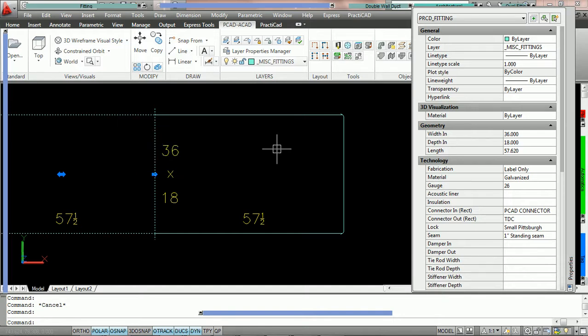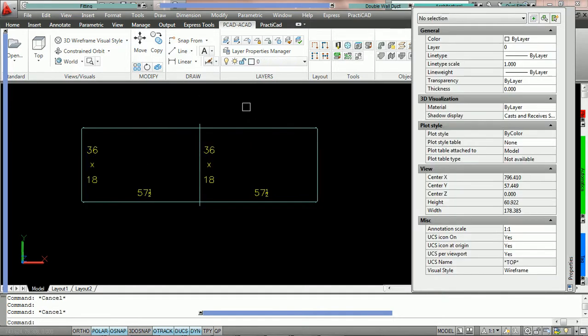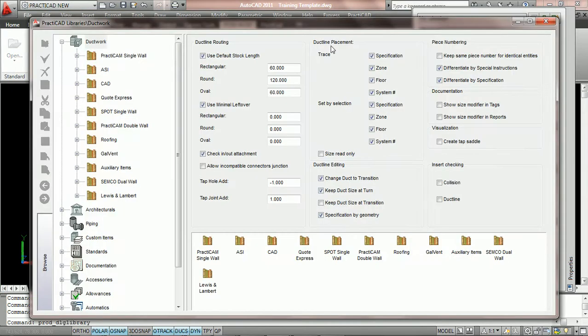Now, one thing to keep in mind is that the entire mechanism we just showed you will only work in this manner if in your ductwork options you have the Allow Incompatible Connectors option unchecked. And we have separate tutorials on that, but to show you where it is, we're going to go into my library. And under ductwork libraries, you have the option here to allow incompatible connectors. This option we recommend to always keep unchecked.